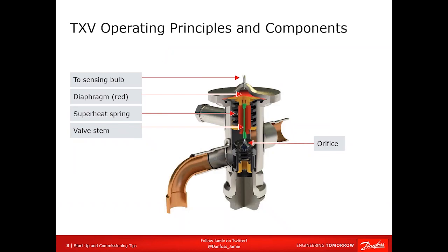So let's look inside of it. This is one from our ice machine kit. You can see that refrigerant enters in on the left-hand side, goes out at the right. On the upper left is the superheat adjustment spindle. At the top, you have your diaphragm. The beige thing underneath there is your pressure plate, force plate. And then you have your superheat spring and your valve stem in green. So when the bulb pressure exceeds the combined evaporator and superheat spring force, it drives that valve stem down, pushing the pin in the orifice downwards and opening up that orifice and allowing flow through it. And the greater the pressure developed by the sensing bulb, the further down it's going to open that orifice until it's fully stroked open.